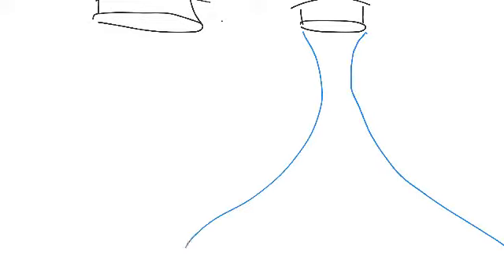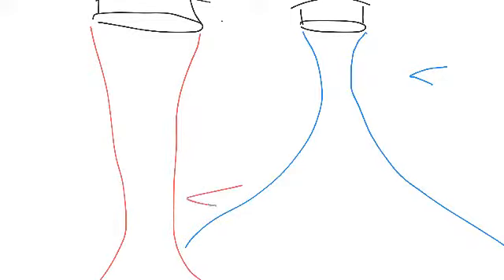And so we've already said that we can change the focus by changing the diameter of the crystal, or the frequency. So we're not going to change the frequency, we're just going to change the diameter. And what we get with this one, let's do it in blue here, with the little one is it focuses down and then it spreads out, and that gives us a focus right there. With the larger one, it's not going to focus down until it gets deeper into the body. Okay?